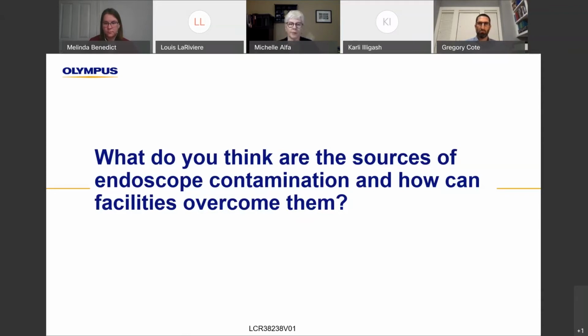So I'll stop there, but that's the microbiology background in terms of where we get contamination. To summarize: it could be failure of reprocessing, maybe due to biofilm buildup or inadequate final water rinse. It could also be contamination from an inadequate final water rinse that has organisms in it, coating the endoscope. Another source is inadequate manual cleaning—putting a scope that hasn't been properly cleaned into the AER makes it harder for the AER to do its job properly. And the last is during sample collection, if you're doing culture on a scope and accidentally introduce contaminants into it.